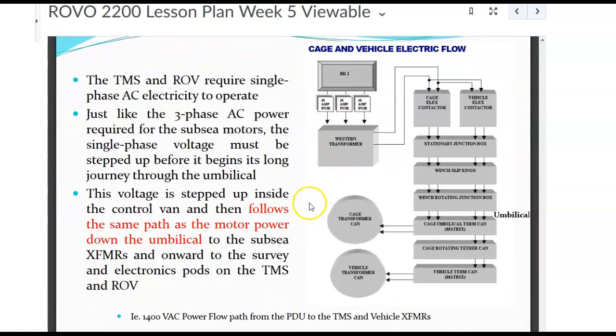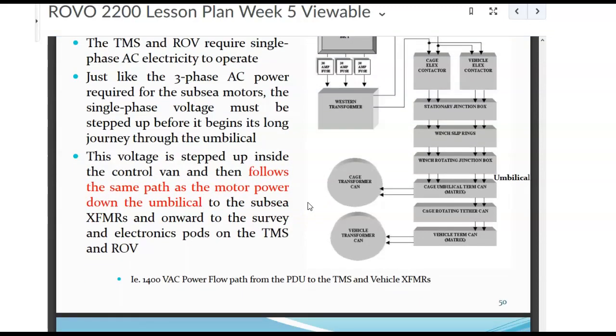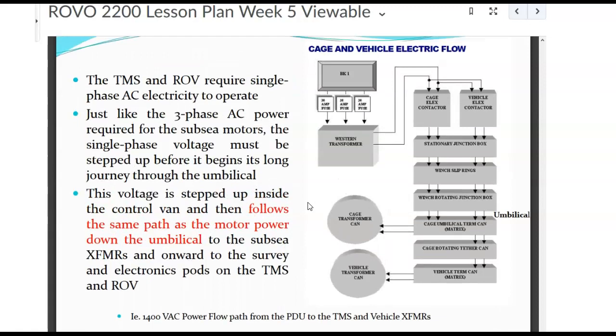So TMS and ROV require single-phase AC electricity to operate, just like the 3-phase AC power required for the subsea motors. The single-phase voltage must be stepped up before it begins its long journey through the umbilical. The voltage is stepped up inside the control van and then follows the same path as the motor power down the umbilical to the subsea transformers and onward to the survey and electronic pods on the TMS and ROV.